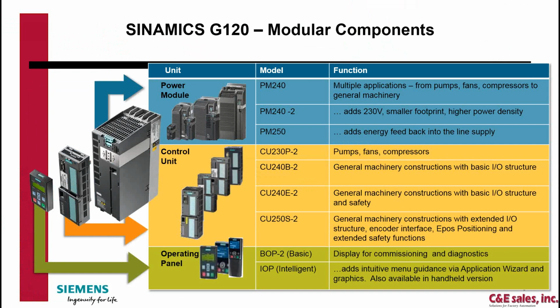The G120 is a modular type drive, so you've got a PM, or power module, so that's going to be the power generation piece of the drive. You've got a selection of control units, which can give you different capabilities or different functionality from the drive. And then you've got this operator panel. Again, we see the BOP, basic, or IOP, which is intelligent operator panel.